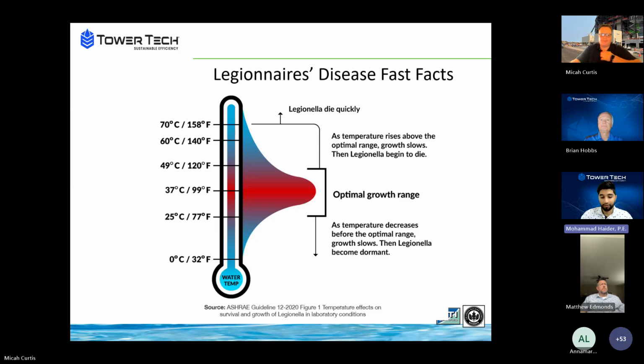And the interesting aspect about this is that cooling towers typically operate with warm water temperatures between about 85 to 100 degrees and cold water temperatures of about 70 to 85 degrees. One thing you'll notice with those numbers is that the overlap is almost exactly within the optimal growth range for Legionella, which is why we're having this conversation today.